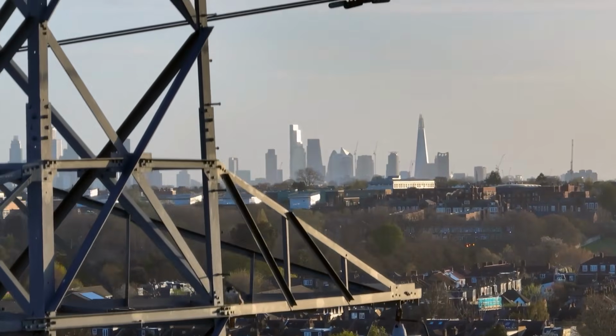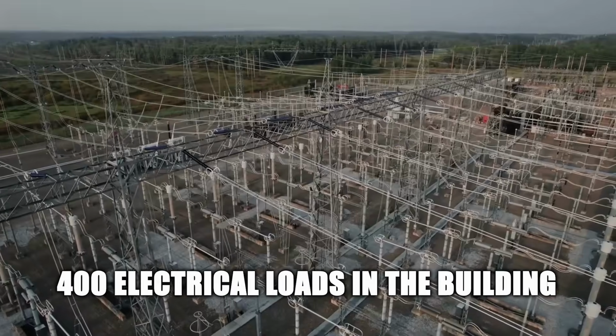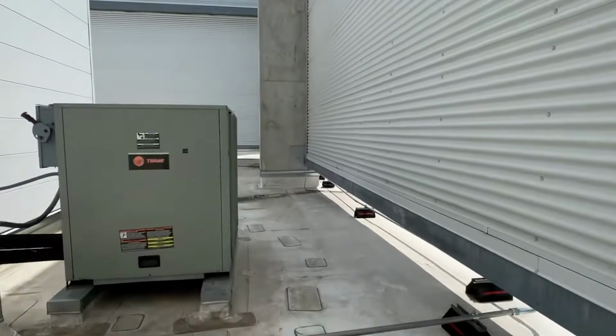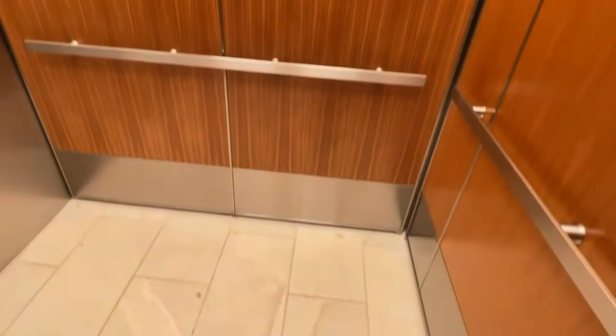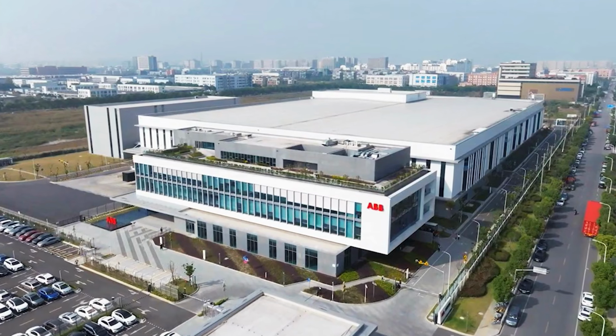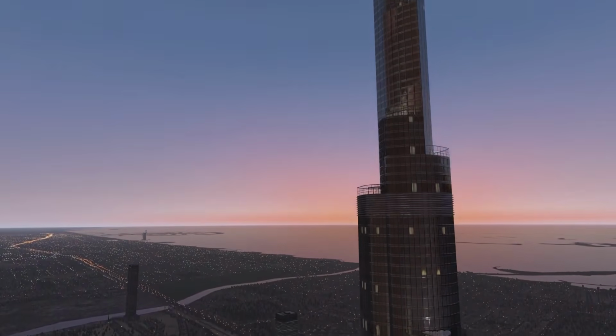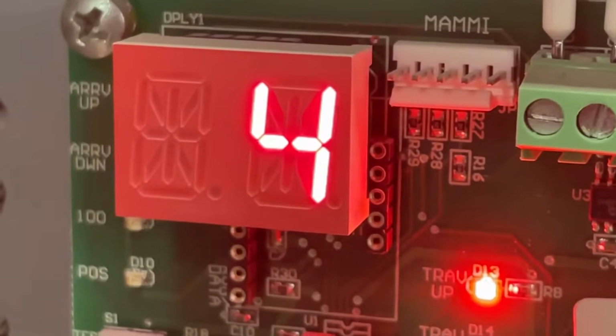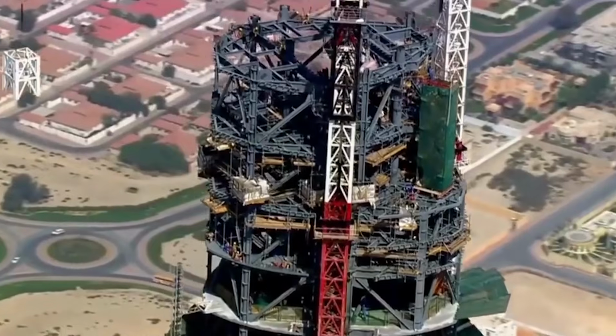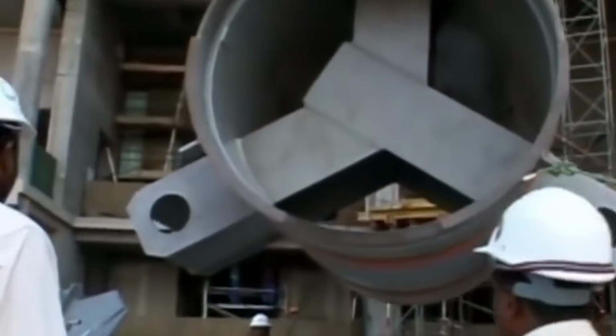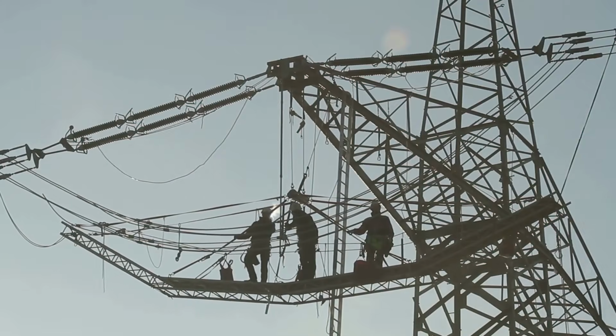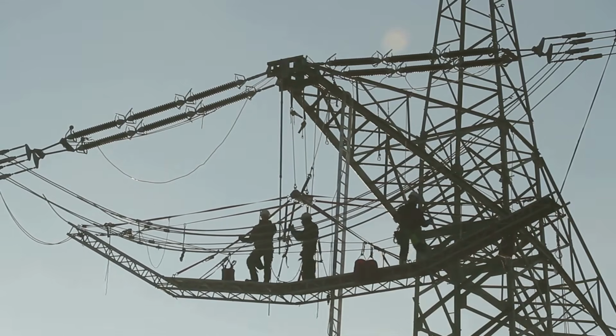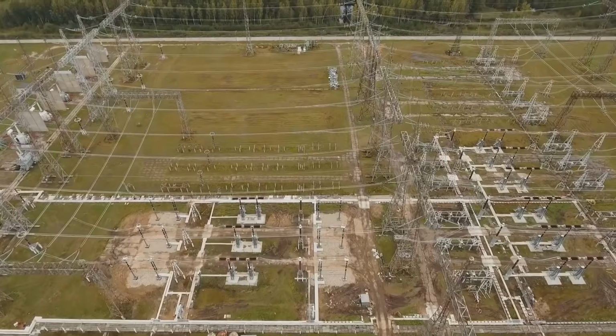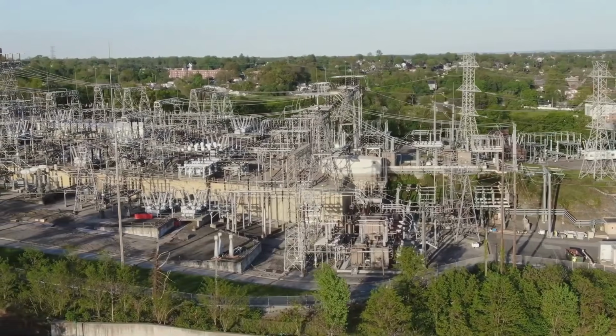The first monumental task was electricity. Getting power reliably to every one of the 400 electrical loads in the building, from elevator motors to fountain pumps to emergency lighting, required a custom-designed distribution network unlike anything previously built for a single structure. ABB, the Swiss-Swedish engineering giant, developed a bespoke smart grid built exclusively for the Burj Khalifa. 50 lightweight gas-insulated medium-voltage switchgear units. 72 custom dry-type transformers, engineered to fit the tower's unusually tight mechanical spaces. The entire network was designed to distribute power at higher voltages internally, reducing energy loss across the enormous vertical distances. It was not off-the-shelf infrastructure. Every component was purpose-built for a problem that had never existed before.